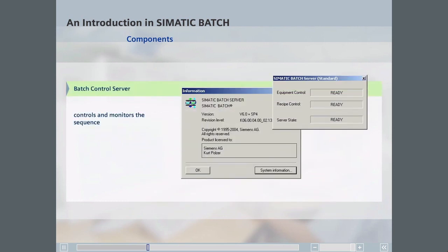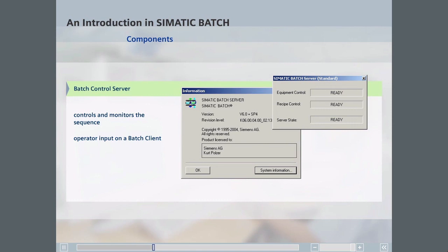The Batch Control Server controls and monitors the sequence of the current batches, while at the same time communicating with the automation systems via the OS. Since all operator input is made from a Batch Client, the Batch Control Server does not have its own user interface. Nevertheless, a client can be installed on the same PC as the server.